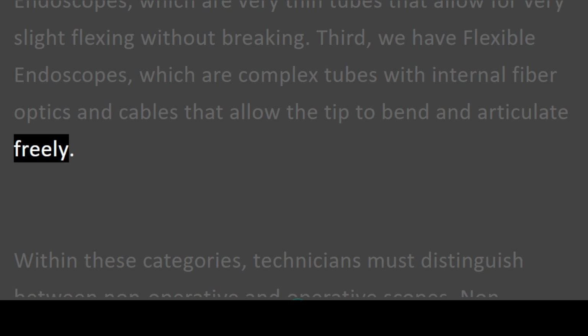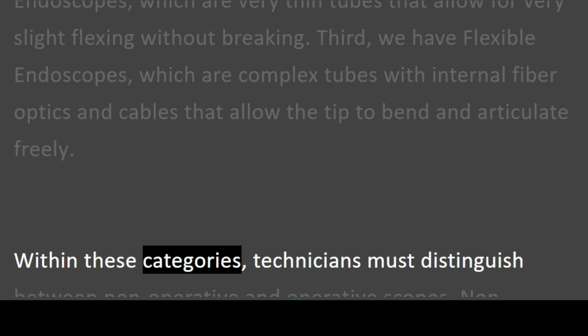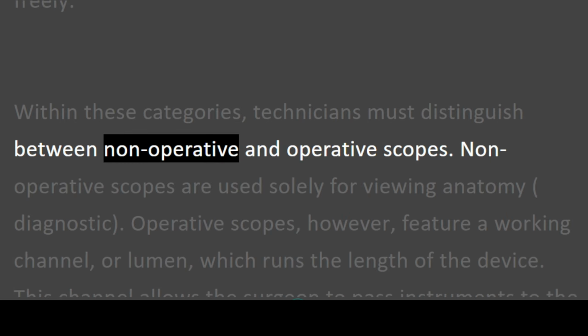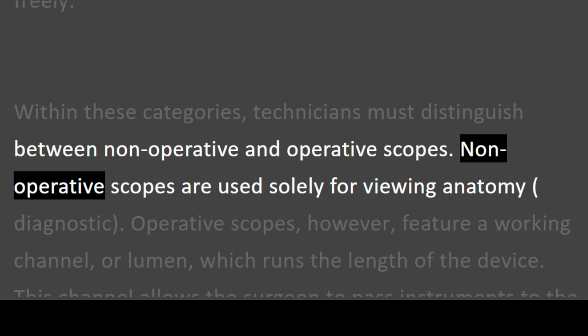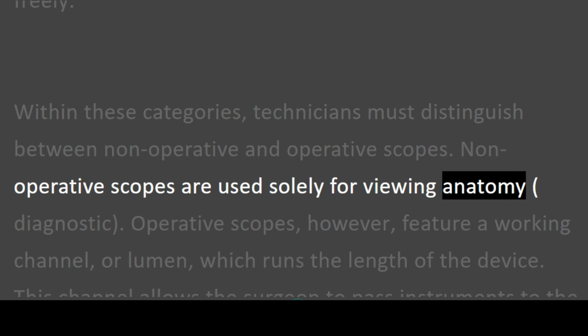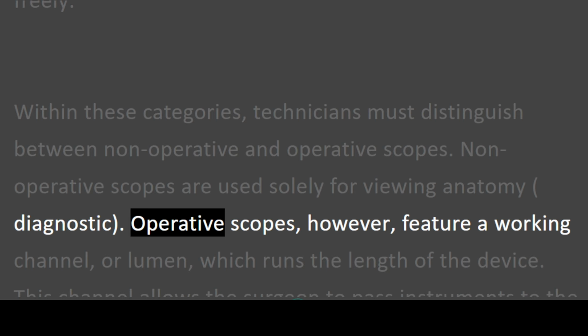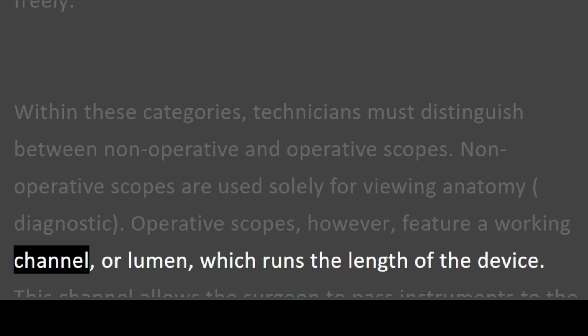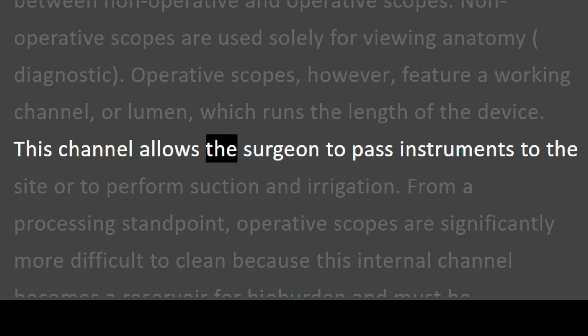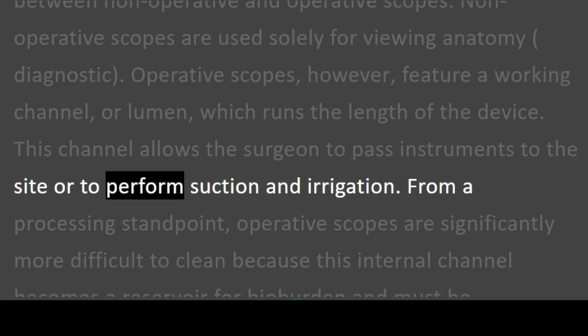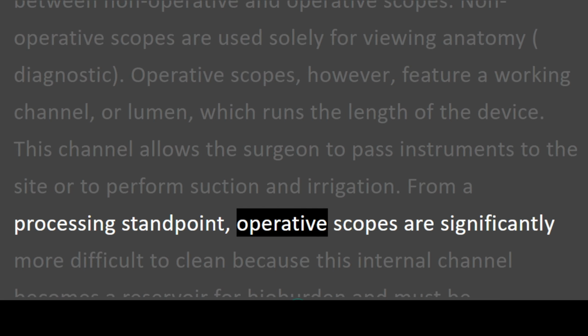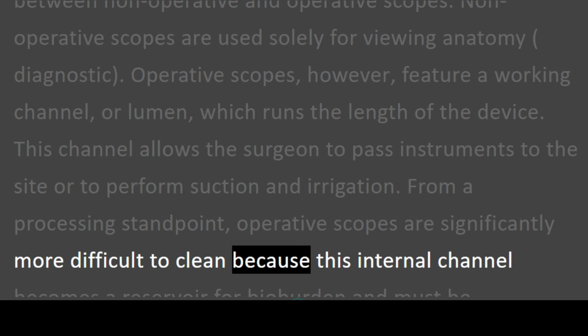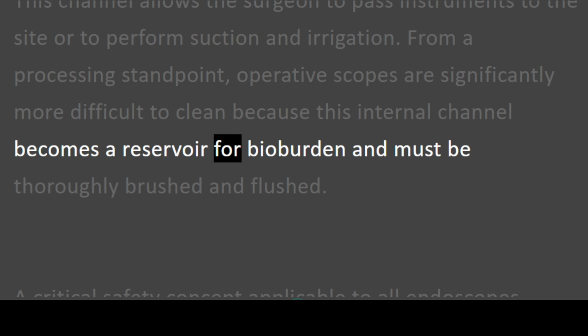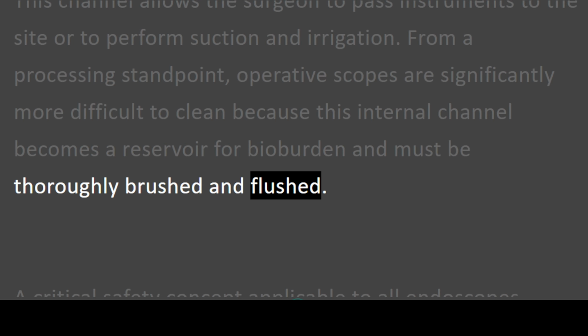bend and articulate freely. Within these categories, technicians must distinguish between non-operative and operative scopes. Non-operative scopes are used solely for viewing anatomy, diagnostic. Operative scopes, however, feature a working channel, or lumen, which runs the length of the device. This channel allows the surgeon to pass instruments to the site or to perform suction and irrigation. From a processing standpoint, operative scopes are significantly more difficult to clean because this internal channel becomes a reservoir for bioburden and must be thoroughly brushed and flushed.